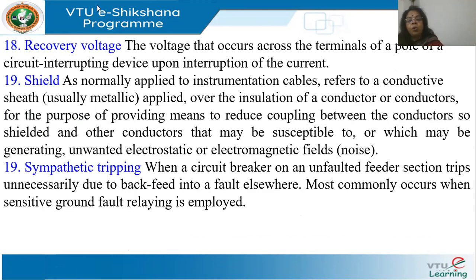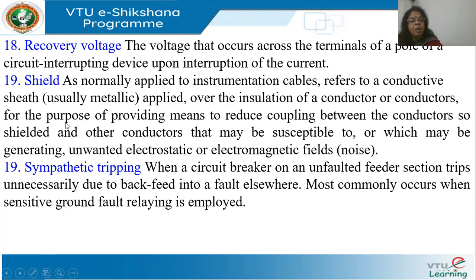Recovery voltage is the voltage that occurs across the terminals after the circuit interrupting process. Shielding is normally applied to instrumentation cables and refers to a conductive metallic sheath over the insulation, providing a means to reduce coupling between conductors and other conductors that may be susceptible to or generating unwanted electrostatic or electromagnetic fields, preventing instrumentation cables from interfering with others.